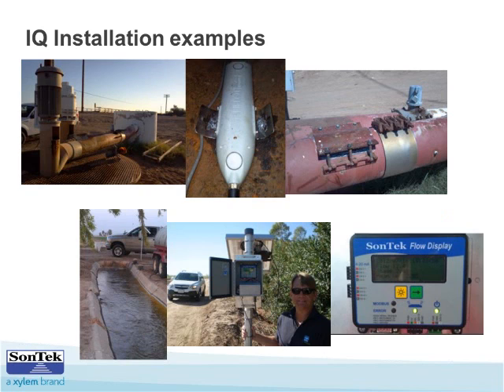It's not just a port, it's right there, okay, there it is. So what we've got here in this picture is the pressure sensor. In the past, and with other instruments perhaps, you'd have a pressure port, I guess I used that term earlier, but it's not exactly accurate. It's not just a port sitting on top of the instrument, it's a flow-through cell, so the pressure sensor is inside this flow-through cell. This orifice is open to the water here, and this orifice is open to the water here, so the water actually flows side to side through the cell. These orifices are not on top, so it minimizes the chance that sediment will just settle in there and clog it up over time.